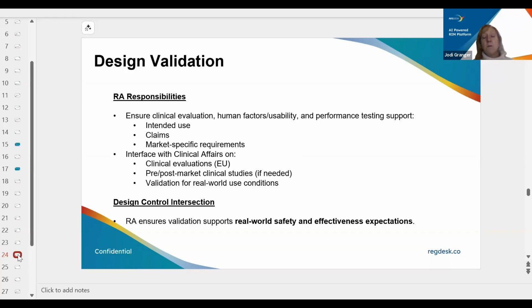For design validation, this is where you'll pull in your clinical evaluation, your human factors and usability studies, any performance testing that is going to be used to support your intended use, your claims, any market-specific requirements. There's close communication between regulatory and the clinical affairs team to ensure that any clinical evaluations that are necessary to gain market clearance are planned out and executed, and that the pre and post-market clinical studies, if needed, have been defined and planned, and that the validation for real-world use conditions have been factored in. So it's important that regulatory support this effort by being in the loop on any validation activities, because they're the ones that are going to weigh in on whether those validation activities support your real-world safety and effectiveness expectations.